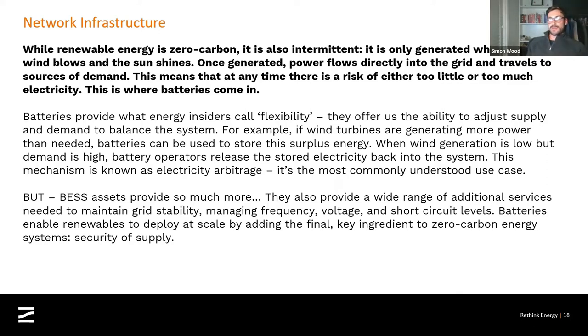And that's known generally as arbitrage. As people generally know it, that is the standard use case for a battery. You could charge the cells up when the wind is blowing or the sun is shining and there is surplus electricity on the system. And then you can discharge that at times of peak demand. I'll go on to explain a little bit more about how that's not the most useful case for batteries, albeit it's the most commonly understood.